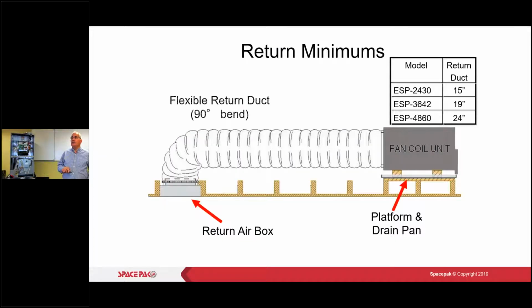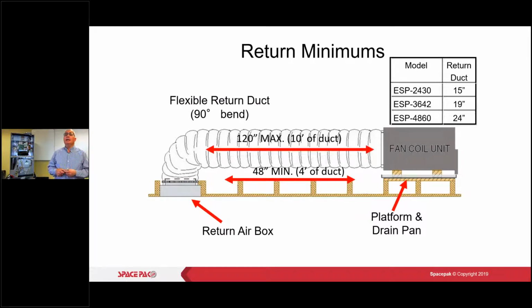What are we showing you here? The minimum length here: 15 inches if I'm at 2 or 2.5 ton, and for 3.5 to 4 ton, you can see 19 to 24 inches. A max of 120 inches or 10 feet, so no larger than that, and there's your minimums, 4 feet of ducting here. Any questions on that? Kind of feels like a speed date, but this is just what we do in the world of SpacePak.